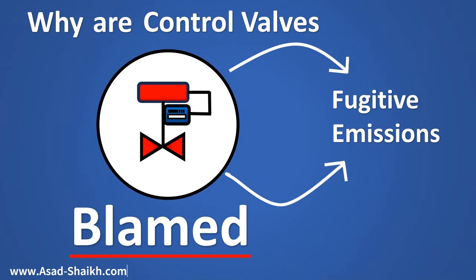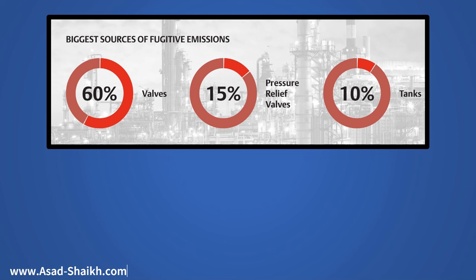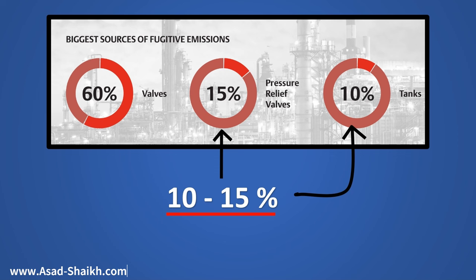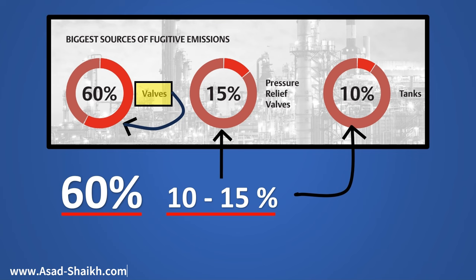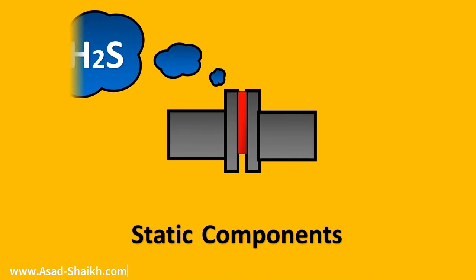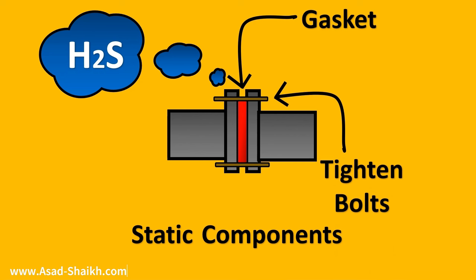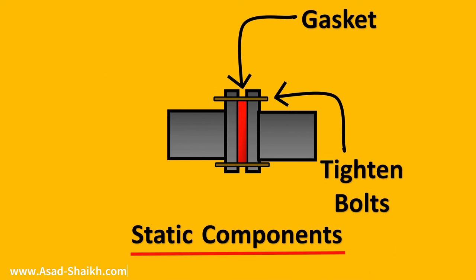Why are control valves blamed when it comes to fugitive emissions? In a plant there are tanks and relief valves available, so why control valves? The reason is, if you look at the stats, only 10 to 15 percent of fugitive emissions come from pressure relief valves or tanks, but a whopping 60 percent is from valves. These are static components, meaning if there is H2S or any fugitive emission happening, you can put in a gasket and tighten the bolts. Once done, because these are static components, you can easily reduce the fugitive emissions.